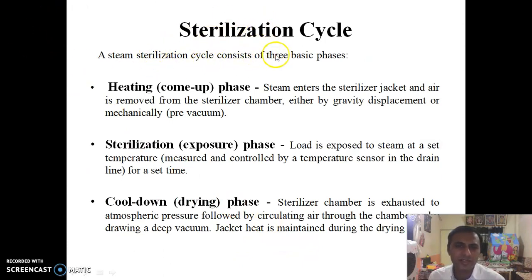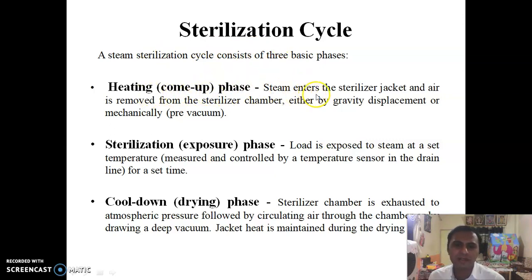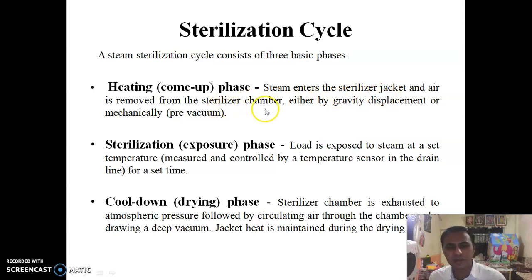The sterilization cycle usually consists of three phases. First, the heating phase: steam enters the sterilizer jacket and air is removed from the sterilizer chamber either by gravity displacement or mechanical means.